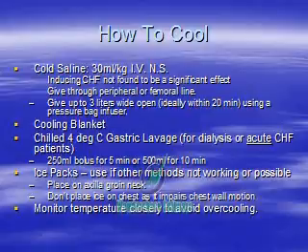And the second thing is cooling blanket. We now have the one where it wraps around the legs and the torso. The leg one, both of them go through one unit. One tube comes out of the machine, goes into one leg. The next tube goes from one leg to the other, and then the final tube comes out the second leg back to the machine as one circuit. Then that way the second circuit or openings are available for the torso unit.